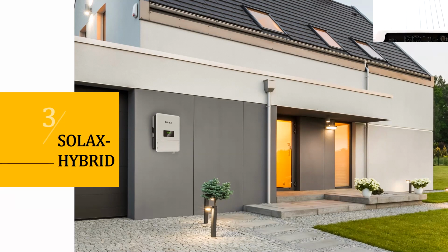You can connect two different rooftops to it. If it were just one, you could only connect one direction of a rooftop to the inverter. So the MPP tracker is basically looking for the best, most efficient working point - I have the word in German but I'm struggling to find it in English right now, I hope you understand anyway. Basically, an MPP tracker can connect a whole array to it, and if you have more MPP trackers not connected to each other, you can use different rooftops and different directions without interfering with one another. So basically it's an input of the inverter.